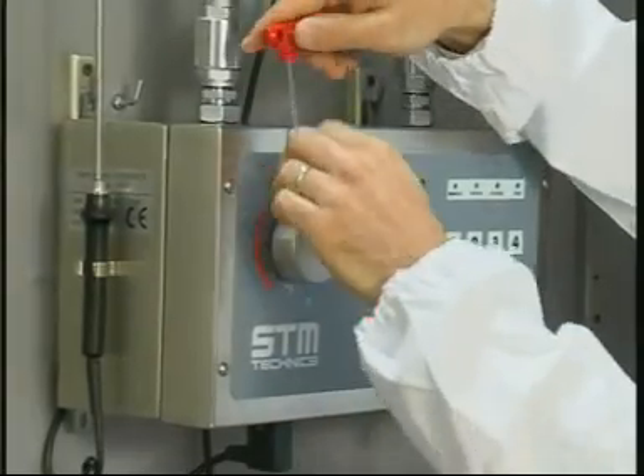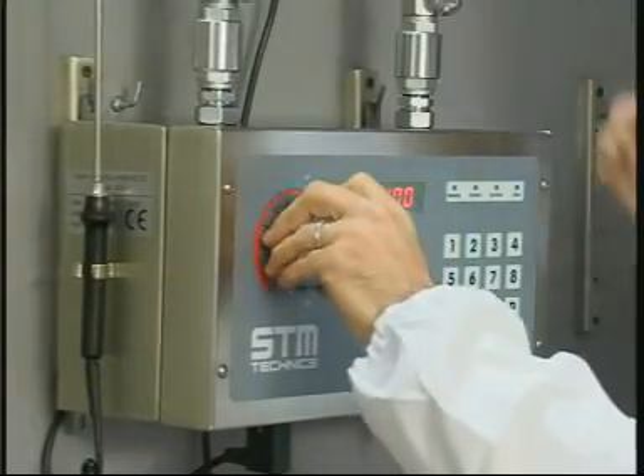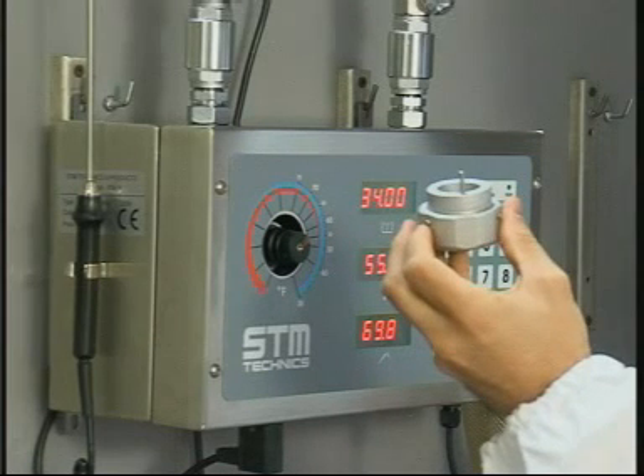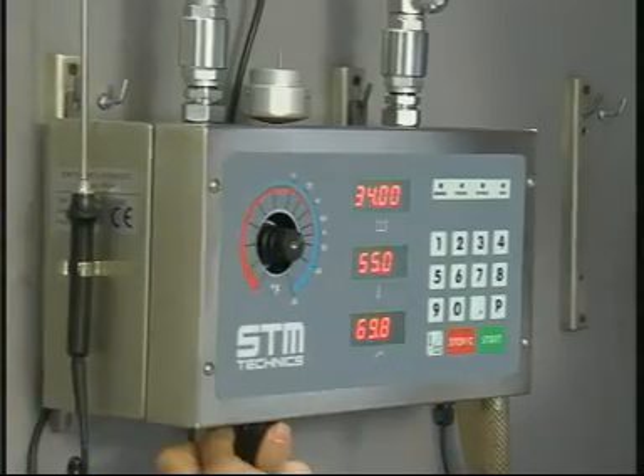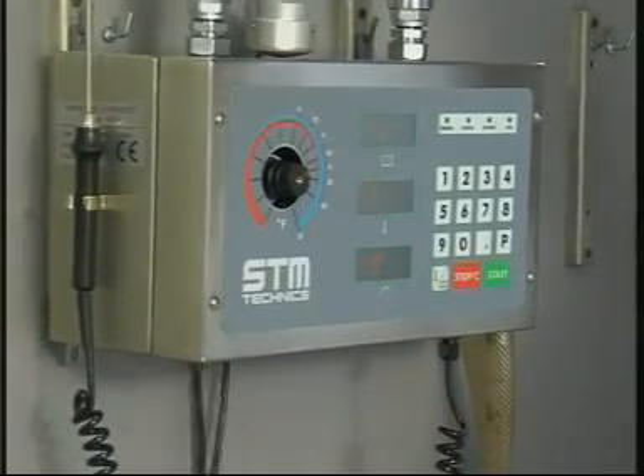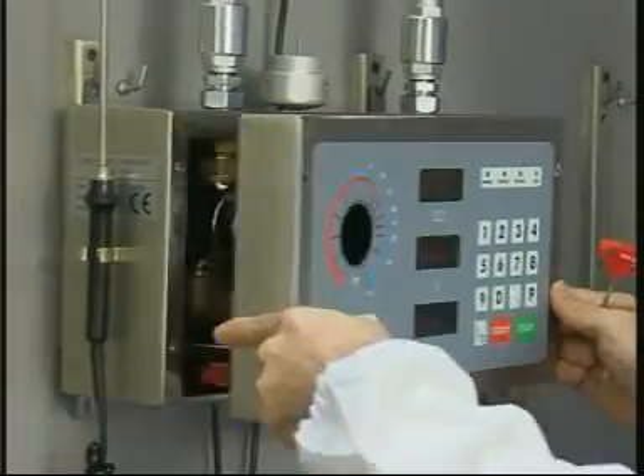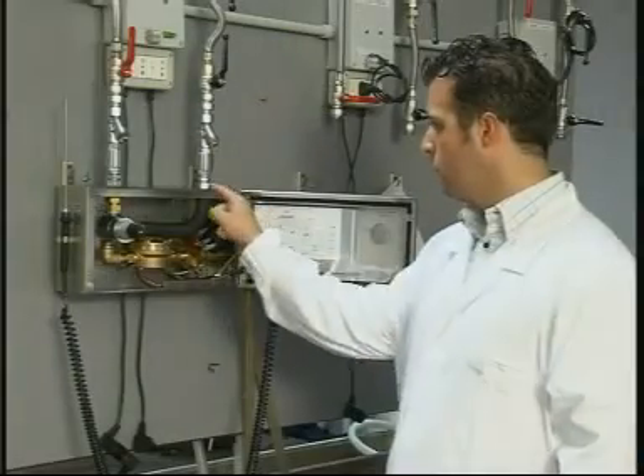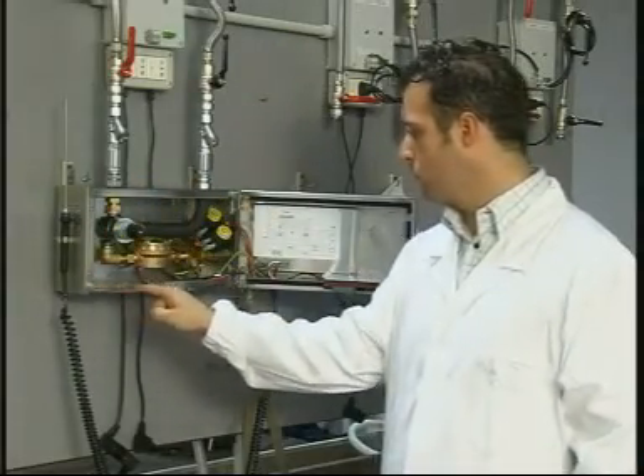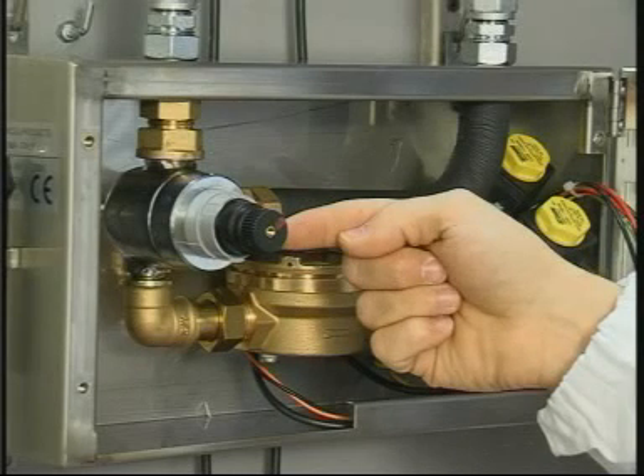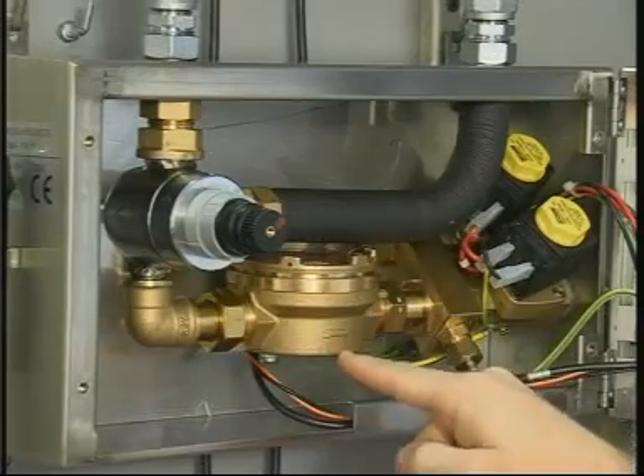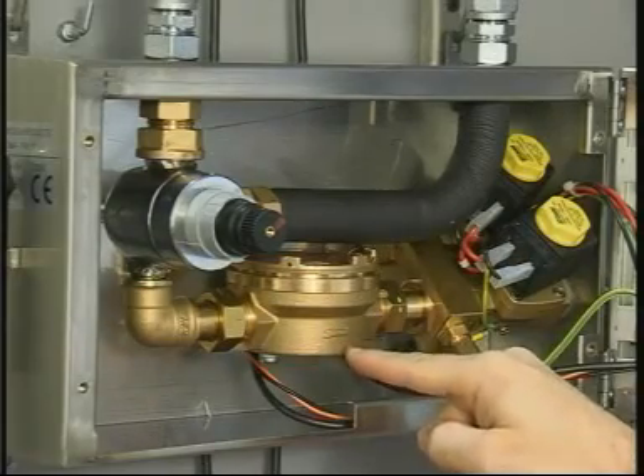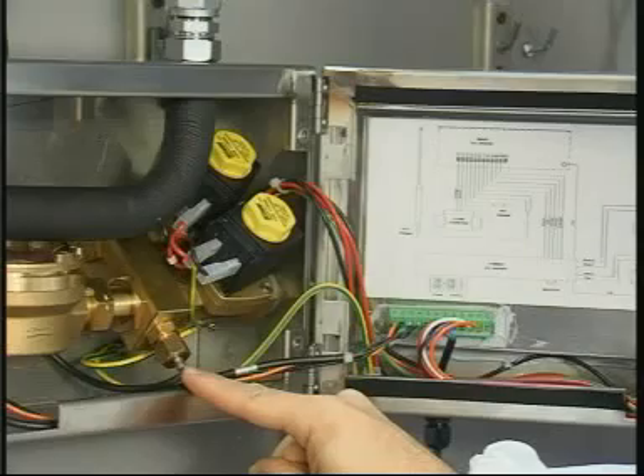To open the machine, switch off the power supply. Unscrew the 3 grub screws on the knob and then extract the knob. Take off the 4 or 6 screws at the front and turn the cover. On the inside of the hydraulics box, the following parts can be found: the mixing unit, the litre counter and the electro valves assembly, with the fitting for the internal probe.